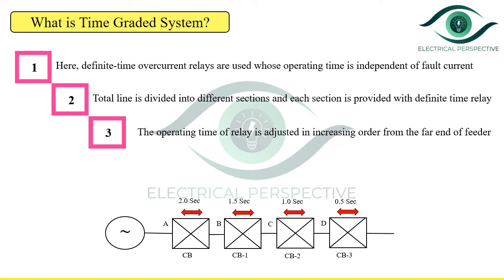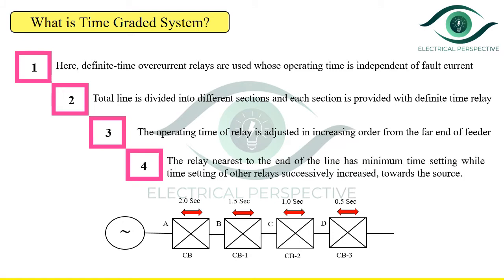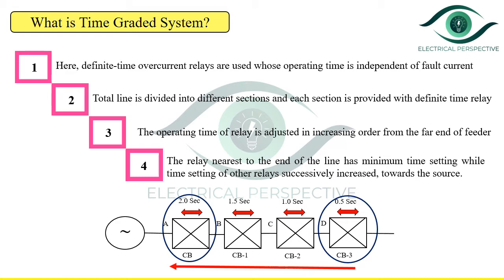To achieve the objective that the smallest possible part of the system is isolated in case of fault, the operating time of the relay is adjusted in increasing order from the far end of the feeder. The relay nearest to the end of the line has the minimum time setting, while the time setting of each relay successively increases towards the source. As seen in the figure, the relay nearer to the load end has the minimum time setting of 0.5 seconds, increasing to a maximum of 2 seconds near the source end.